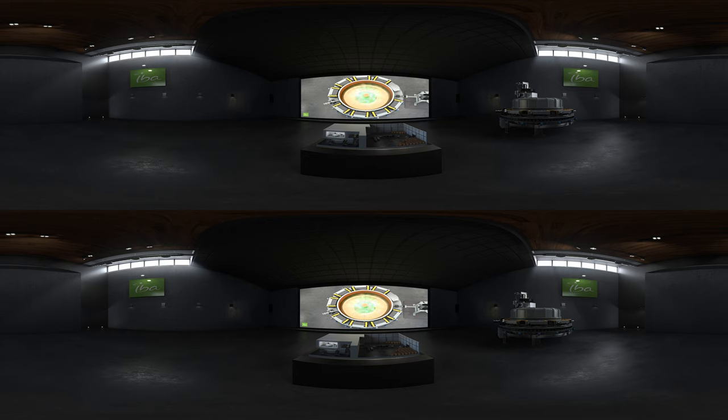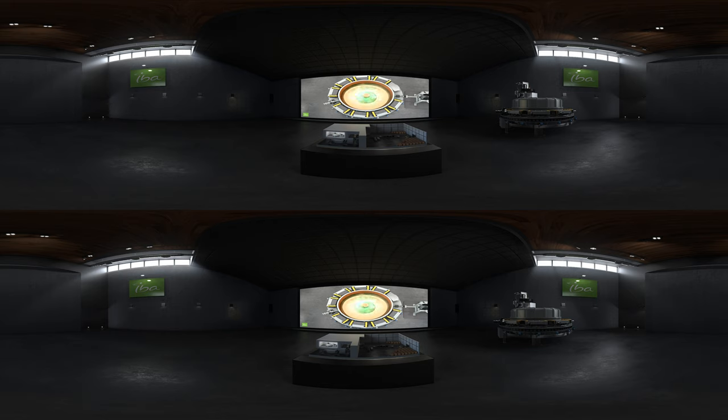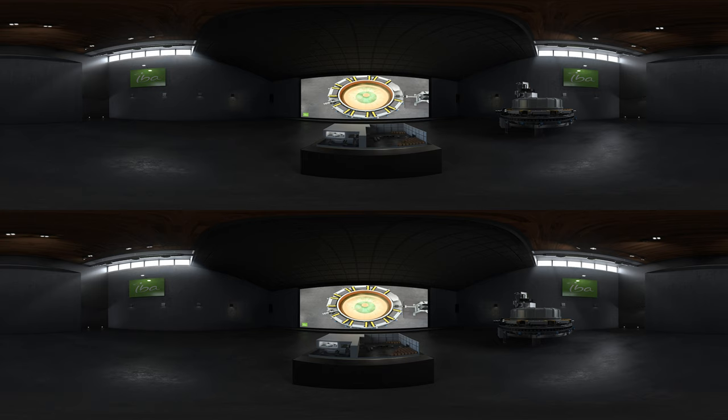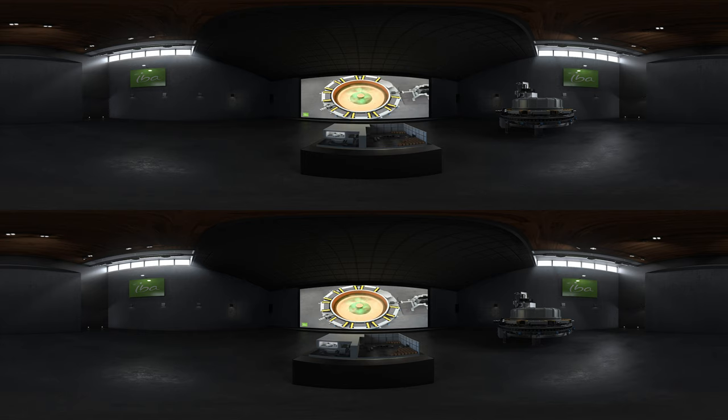After passing through the magnets where they are bent, the electrons are sent back through the cavity. At each pass, they are accelerated by a fraction of the final energy required. When reaching the final energy, the electrons exit the cavity by following their way straight forward through the beam line. If a lower energy is required, another beam exit can be chosen just by switching off the deflection magnet corresponding to this energy.